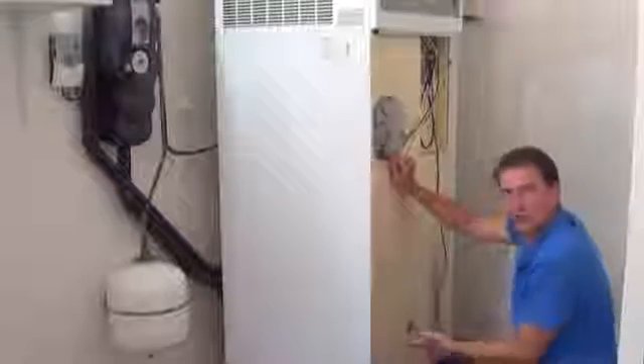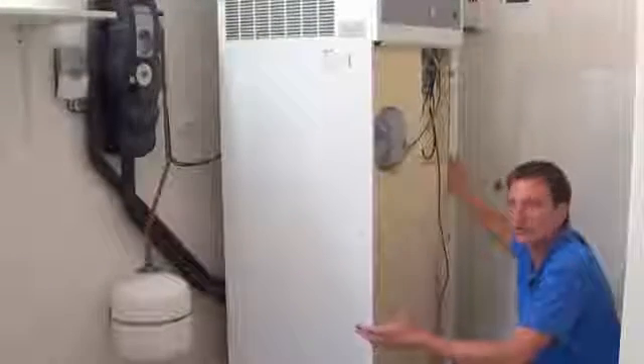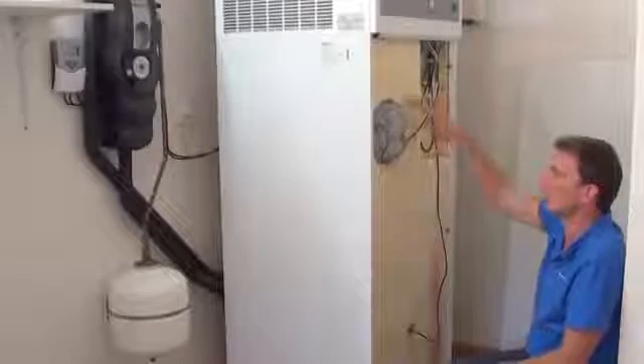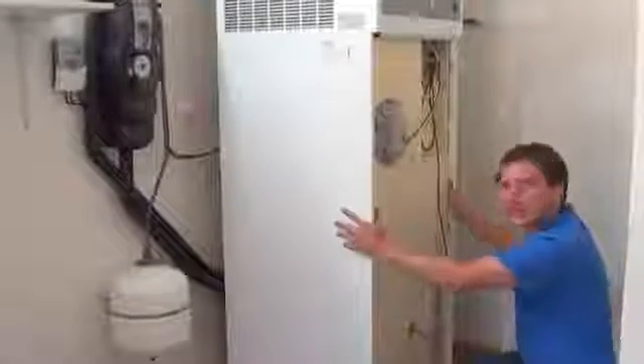So as long as you have solar energy, the heat pump will never ever switch on. This is how you marry a solar system and a heat pump together. The trick is actually the vertical tanks. You cannot have this effect with horizontal tanks. That is why every single machine that we're importing from Europe comes in a vertical tank. We cannot buy horizontal tanks, and this is a problem that we have, in that we are trying to create some awareness in that if you want to save energy, you have to go for a vertical tank. This is the magic, this is where the secret lies of marrying these two systems.